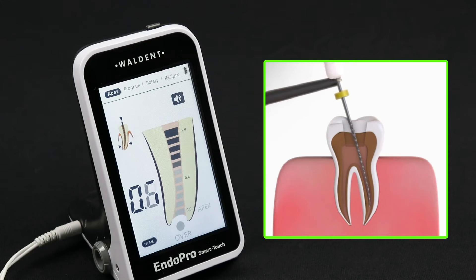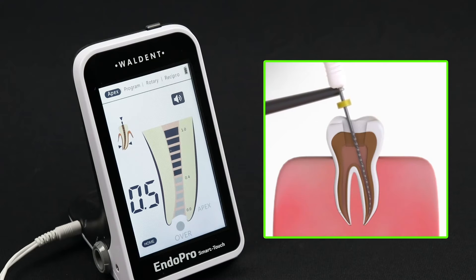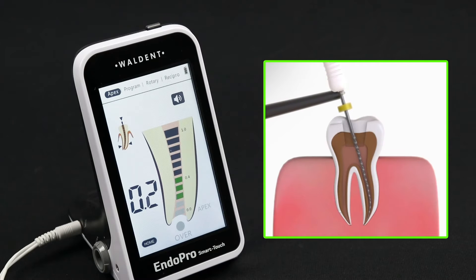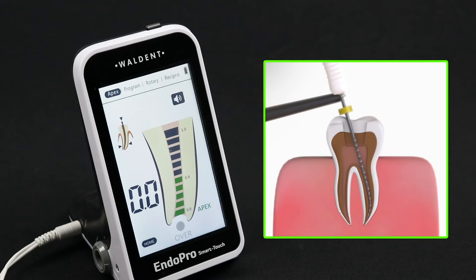When the file is far away from the apical foramen, the blue indication bars are displayed. When the file is nearby the apical foramen, green bars are displayed. When the file extrudes the apical foramen, red bars are displayed.